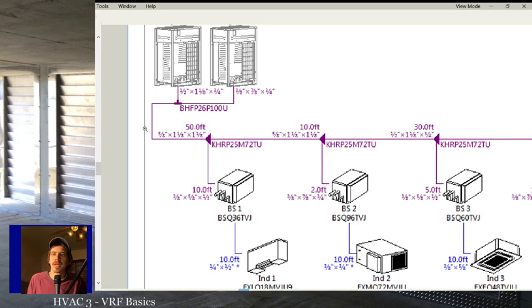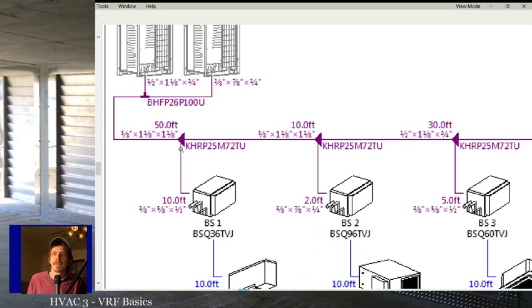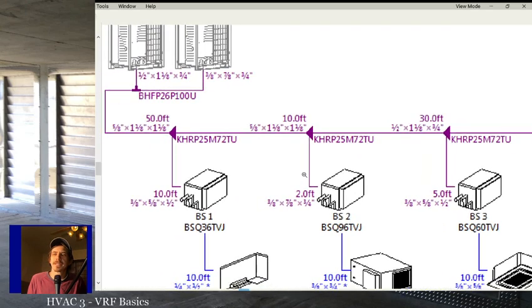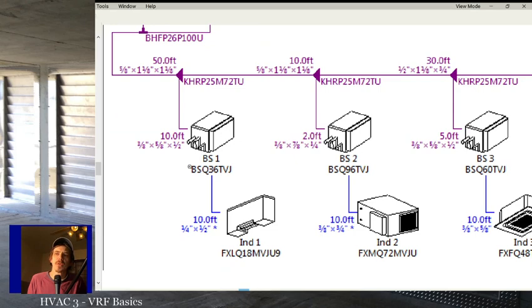So you'll run those down. They run in a bank of 3. And then you'll Y off to branch selector boxes, right? And these branch selector boxes are what switch the indoor units between heating and cooling. So all that's really inside here is a bunch of solenoid valves. And those solenoid valves are either sending liquid to the indoor unit and suction comes back, or they're sending discharge to the unit and liquid comes back. So from your branch selector to your indoor unit, there are only 2 pipes. There are 3 pipes going into a branch selector, and there are 2 pipes coming out of a branch selector.